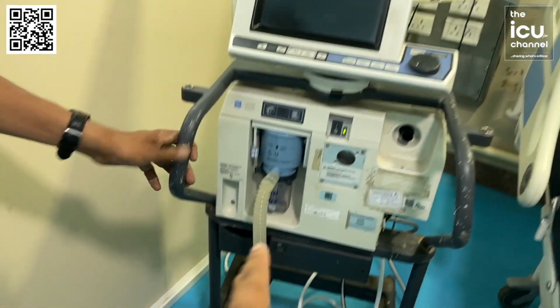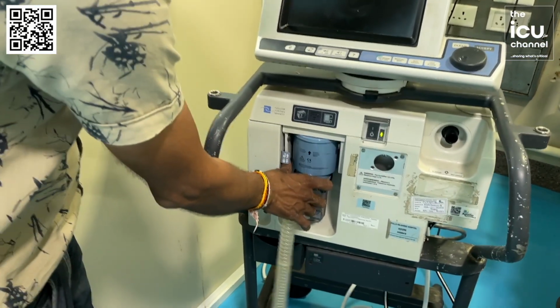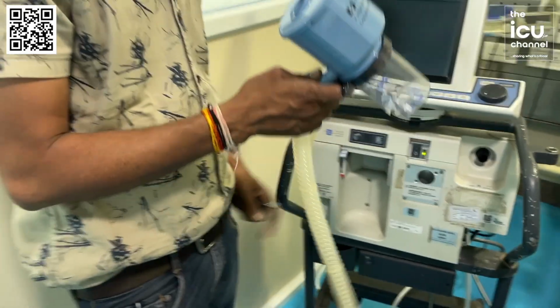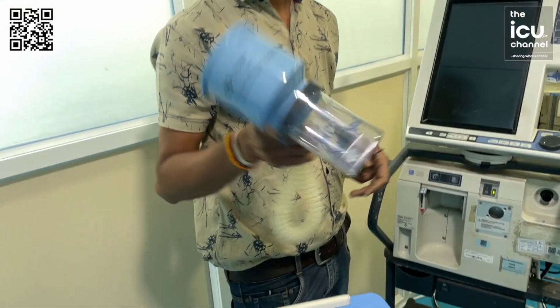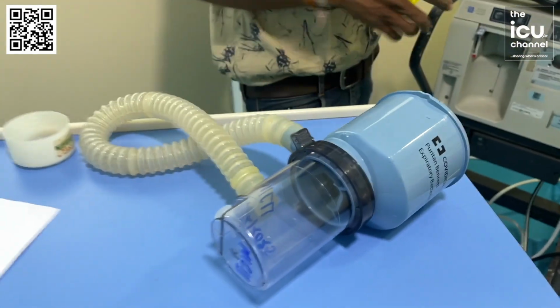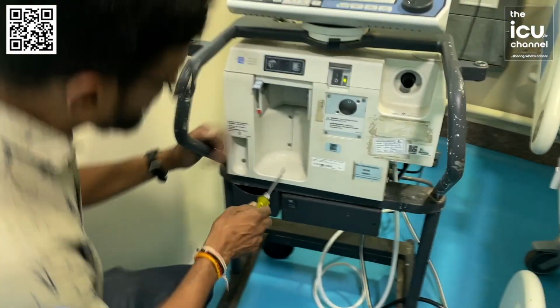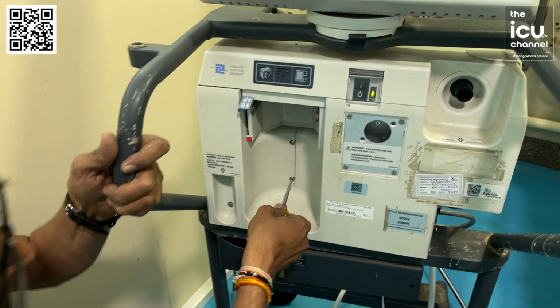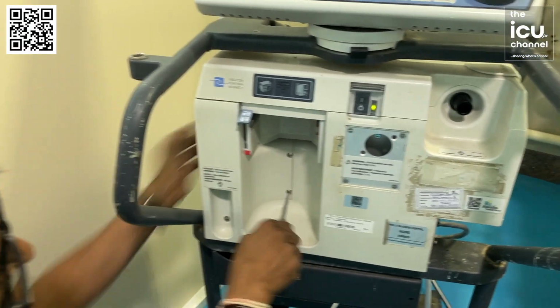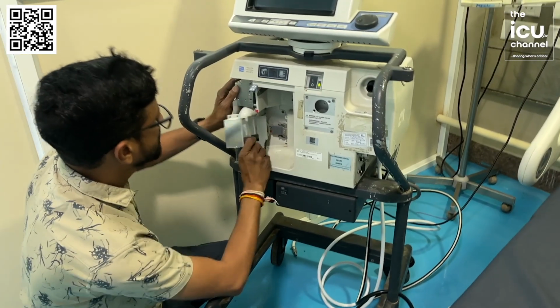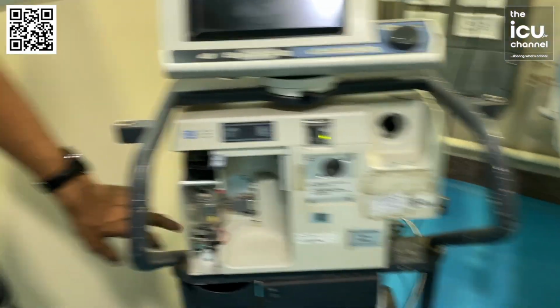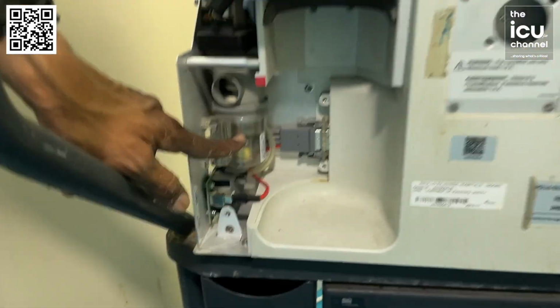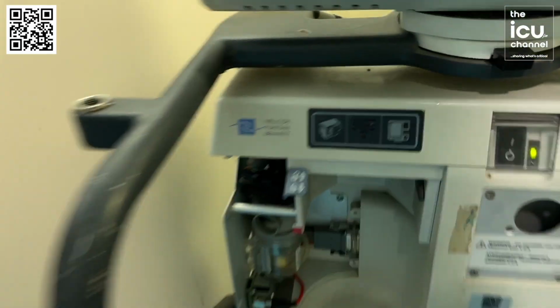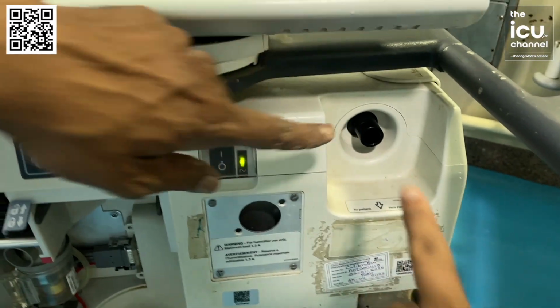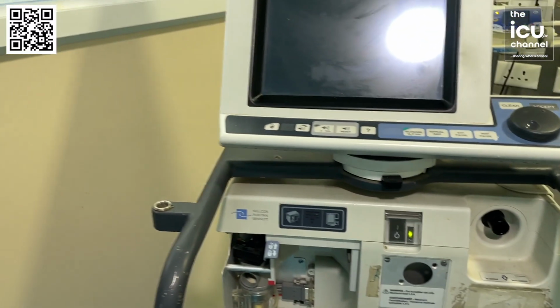So this is the expiratory side of the ventilator. You can see this is the expiratory limb, and this is the expiratory filter. What this does is filter out all the bacteria and impurities which are coming from the expiratory port of the ventilator, and then we'll move on to the inside of the expiratory side, which contains the flow sensor and the leak valve. So Pawan is opening the expiratory side of the ventilator, and now you can see he has opened it, and this is the expiratory valve. So how does the air come to the expiratory side? Once it travels through the inspiratory side, the FiO2 air goes to the patient, and from the patient it comes to the expiratory side via this filter.